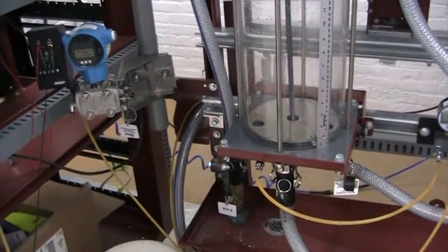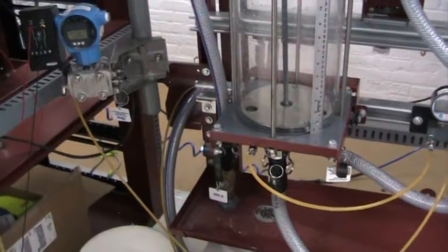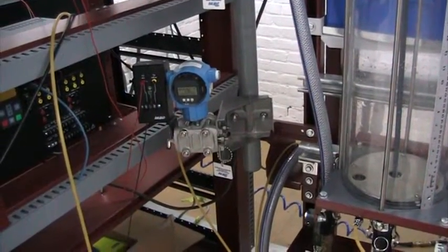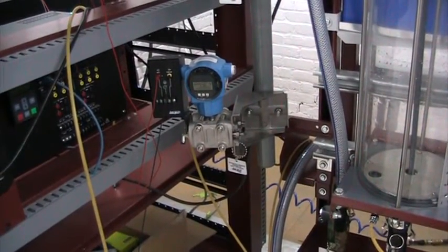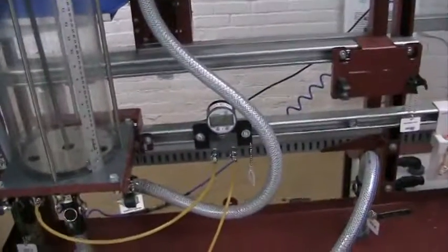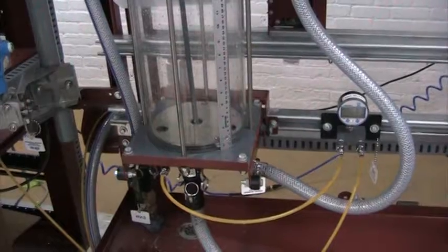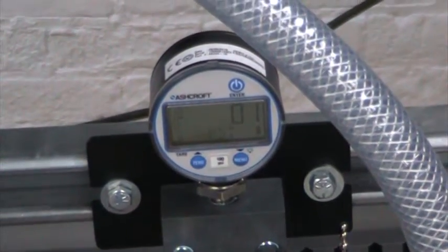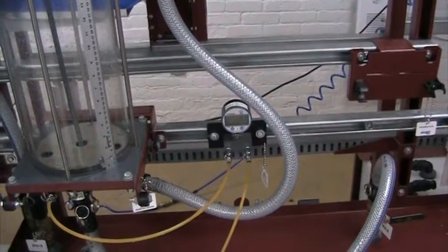Now, of course, after that I turned them on. The differential pressure transmitter requires a little bit of configuration. It takes a little bit longer to configure it than the indicator, but nevertheless, both have to be zeroed when there is no water in the column. So if we take a look at the reading here, it's 0.01. I had difficulty actually getting it to 0. And I notice it's very sensitive even to touch.